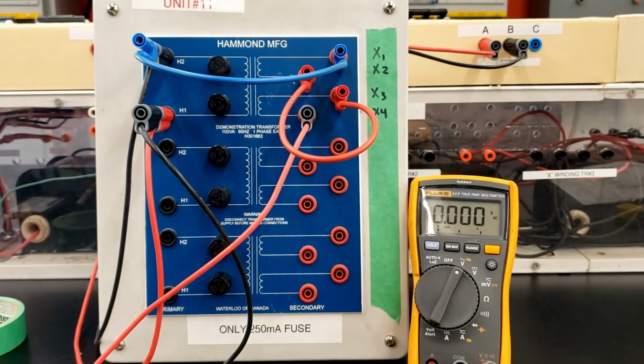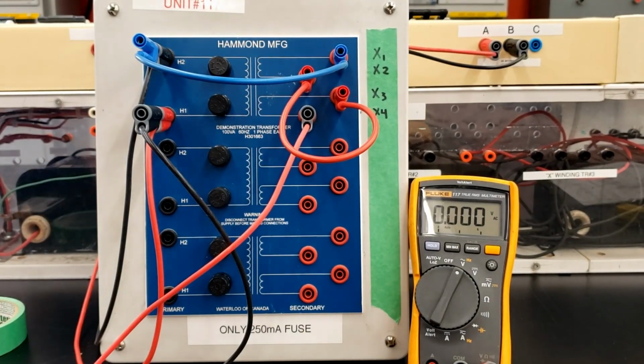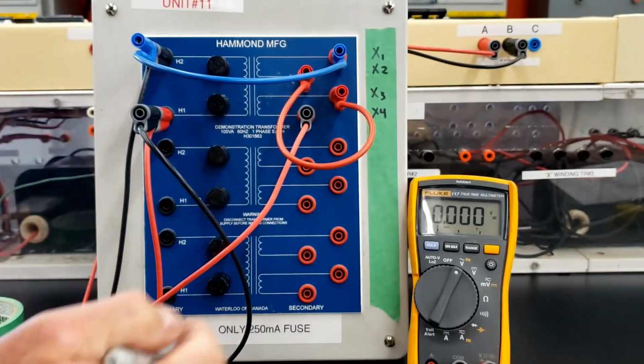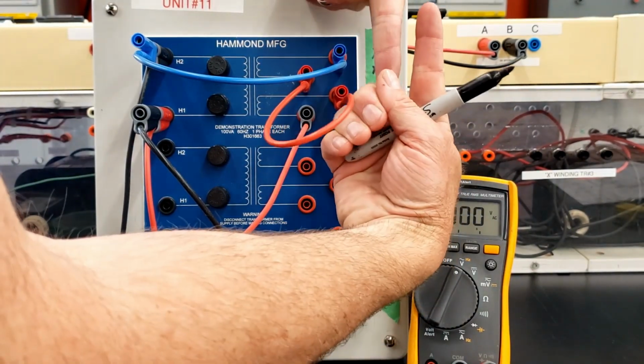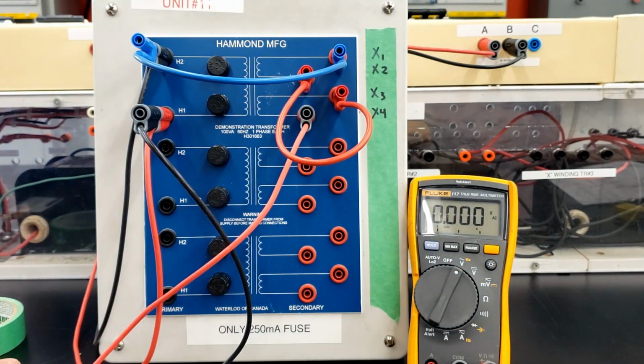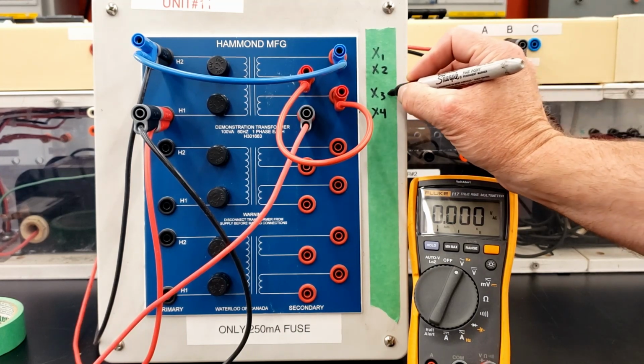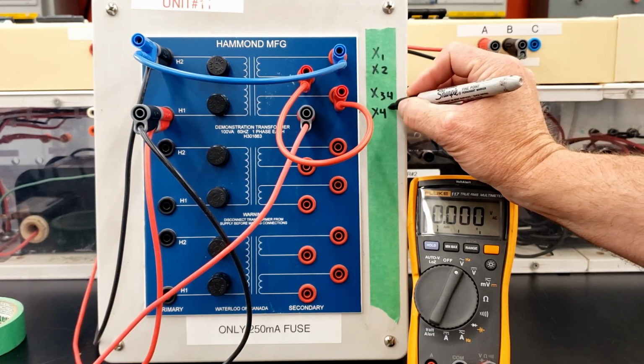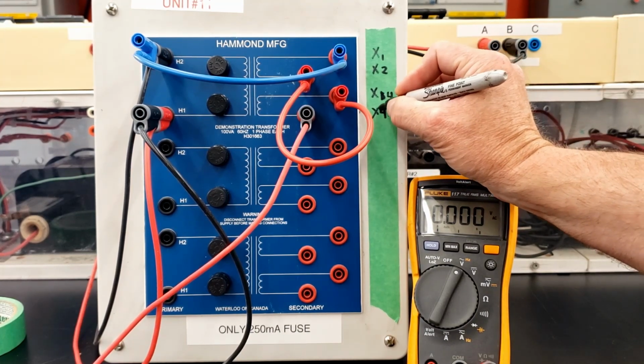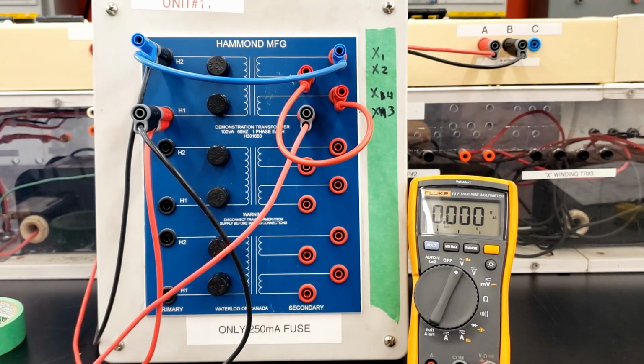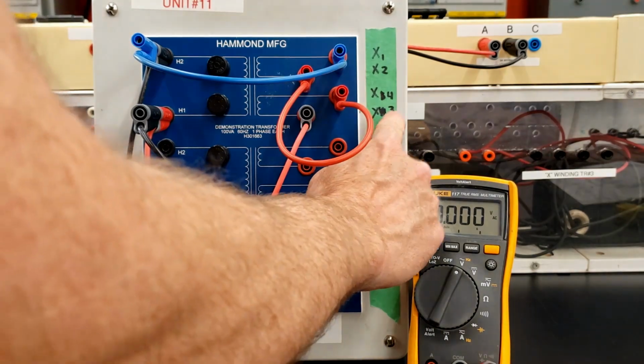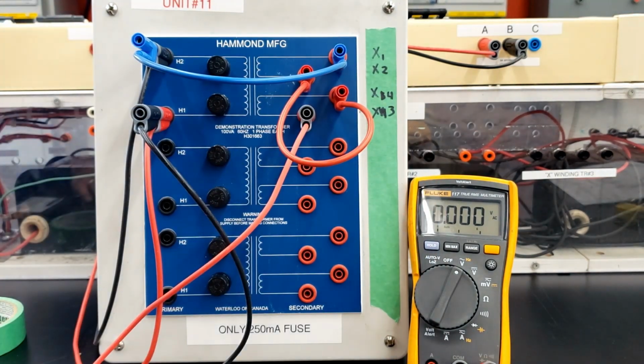Okay, so one of the windings must be backwards, right? Either this one or this one, because at the moment they're pushing against each other. The voltages are the exact same and opposing each other and canceling each other out. So I'm going to do this. I'm going to just arbitrarily change these two. I'm going to say that's 4 and that's 3. Okay, so I'm choosing one of the windings and I'm saying, all right, that's no longer 4, it's 3. That's no longer 3, it's 4.